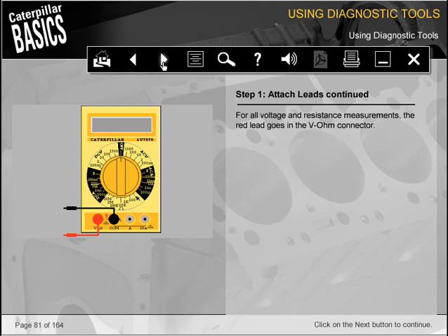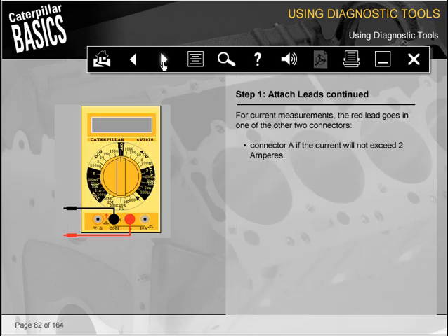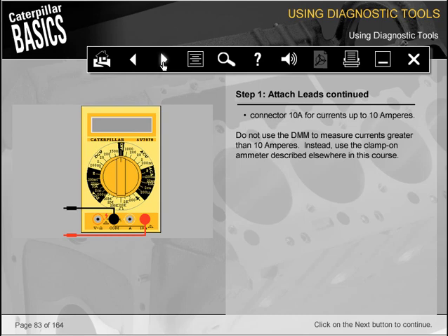For all voltage and resistance measurements, the red lead goes in the V-ohm connector. For current measurements, the red lead goes in one of the other 2 connectors. Connector A if the current will not exceed 2 amperes. Connector 10A for currents up to 10 amperes. Do not use the DMM to measure currents greater than 10 amperes. Instead, use the clamp-on ammeter described elsewhere in this course.